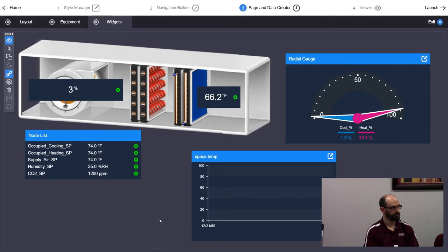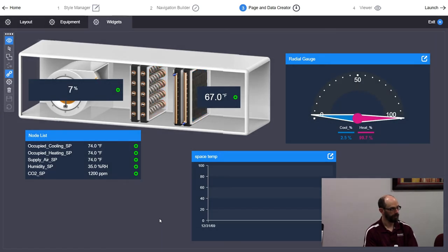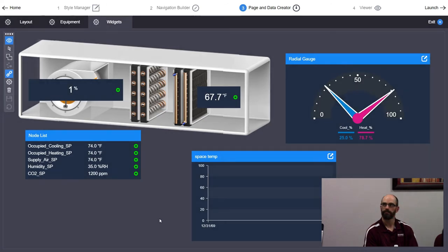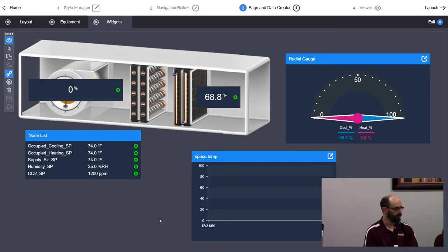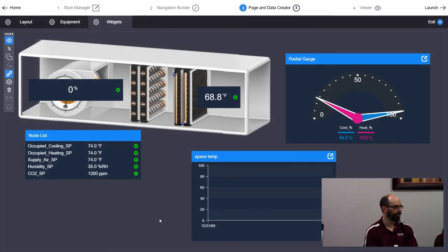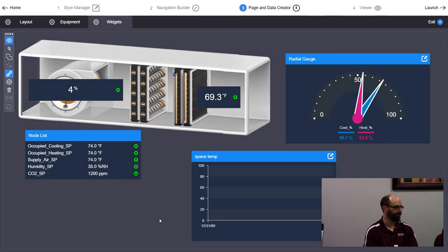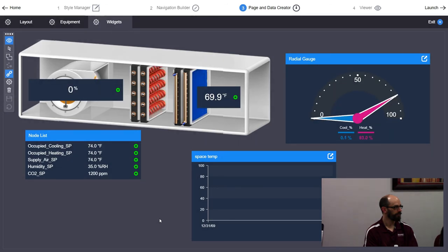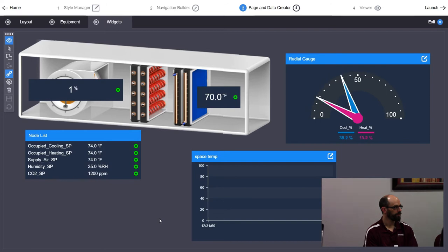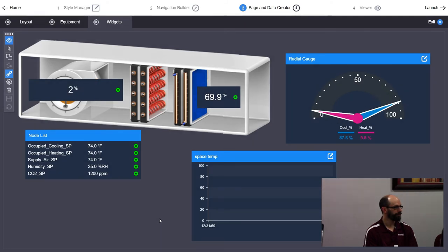For a standalone controller like a home setup, it's different — it pulls trends right out of the controller. The interval setting does make a difference in that case. On COV slash interval trends in Niagara, enabling the alarm extension can screw up the chart plotting — it leaves gaps. It doesn't chart the records that say 'start' next to them in the trend log. If you look in your trend logs and see 'start, start, start,' those won't plot on the chart.